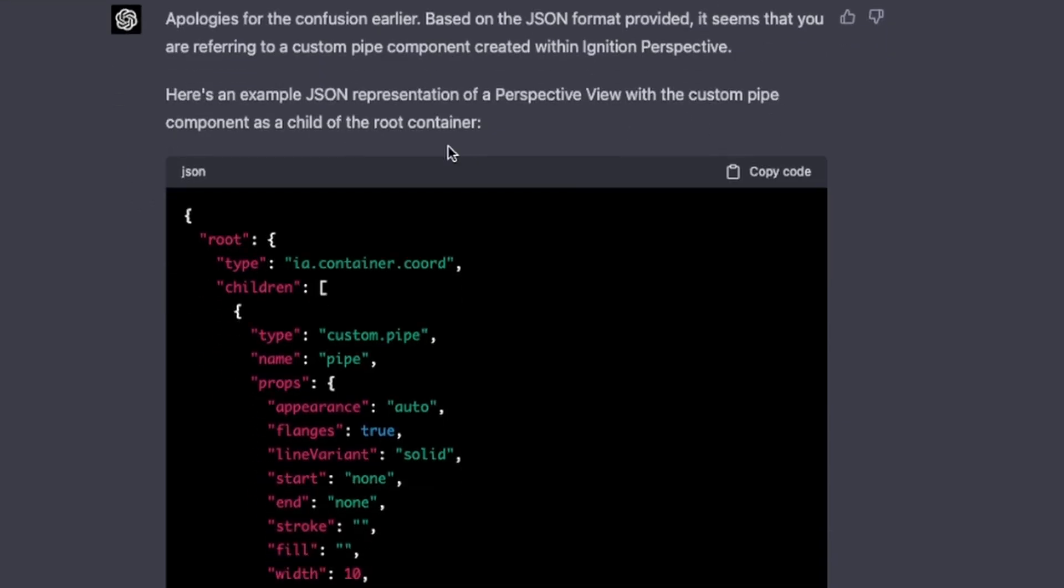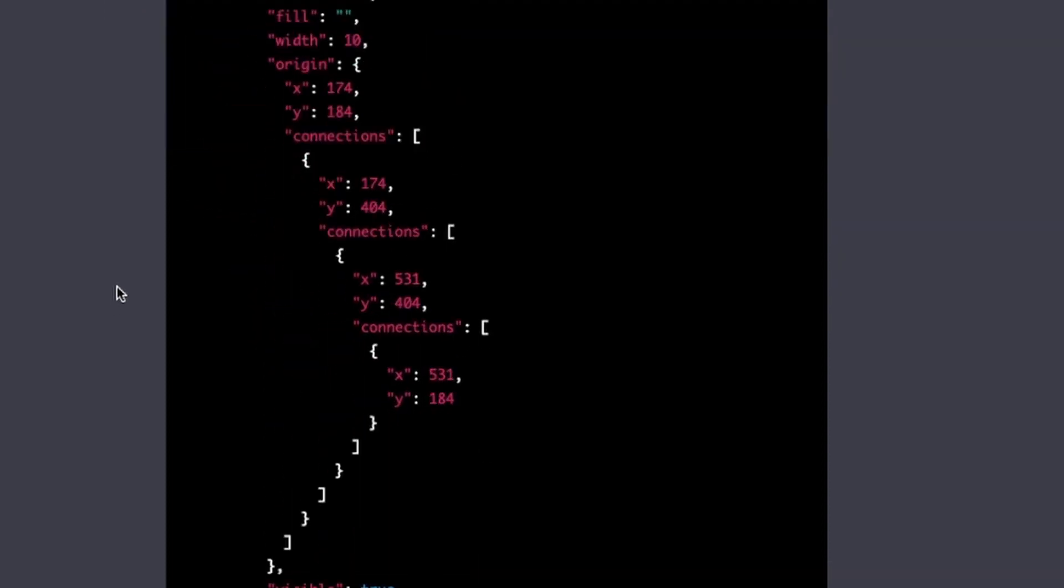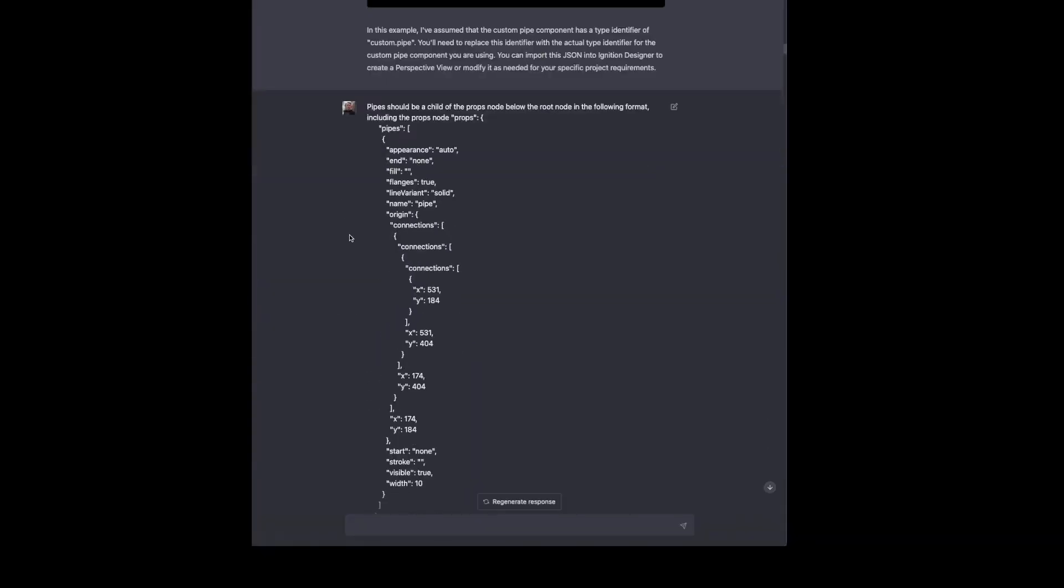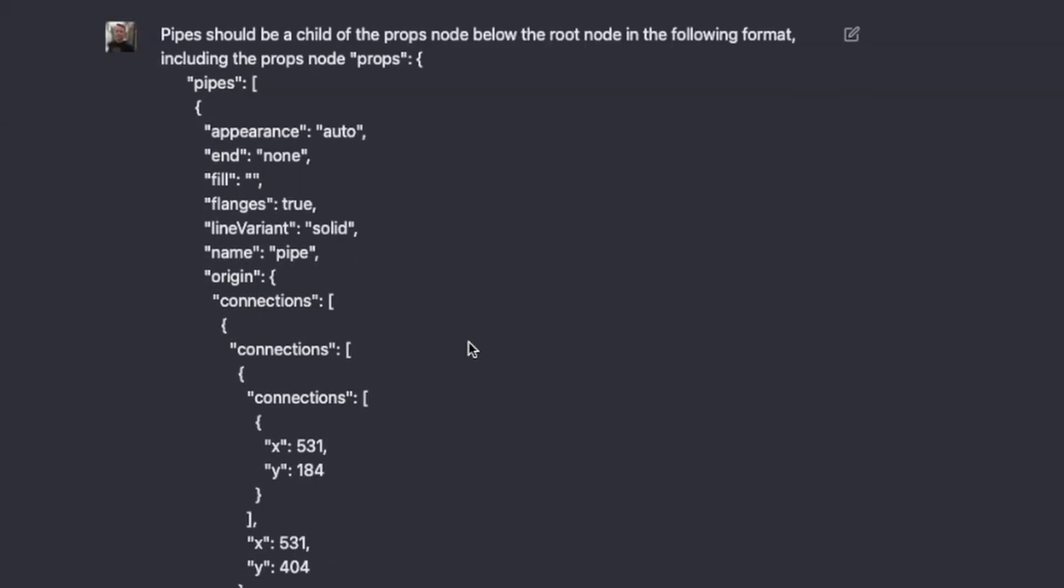So that analyzes the pipe JSON and gives me a representation of what the view would look like with a custom pipe component as a child of the root container. It comes back and it makes some assumptions, type identifier of custom.pipe. We'll have to replace that with an actual identifier for the custom pipe component we're using. And it says we can import that in, which will run into some errors. Most notably, we need to tell it where to place the pipes in the view because pipes are a slightly different piece of the puzzle than a component. They exist on the background layer of the container. They're not a separate component within the container. So this regenerates JSON and brings pipes out from being a separate component and pulls it into the props node in the JSON. And that works.